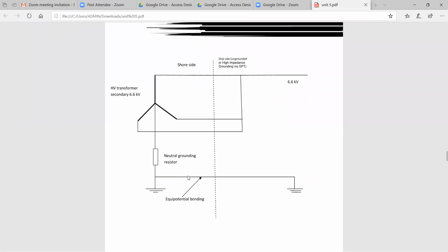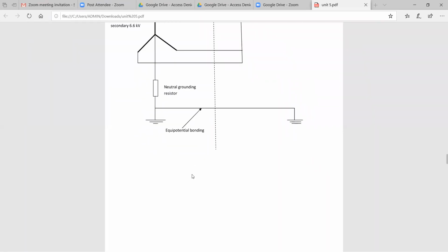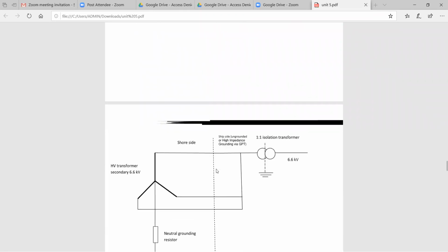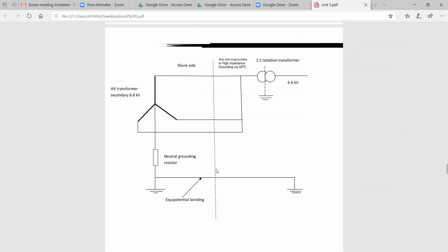The equipotential bonding operations are to be performed. The same concept applies: if the neutral is observed to carry any current, it can be immediately grounded. This concept of operation is performed. Finally, you have operation with the connection of an isolation transformer. The isolation transformer operates with a 1:1 winding ratio. This is the brief review about that.